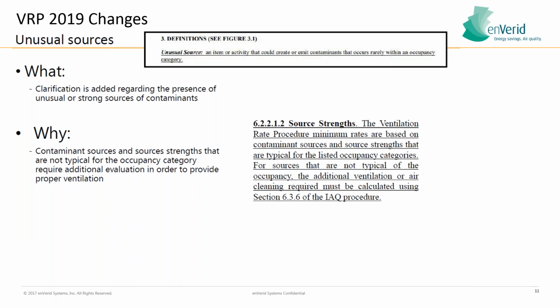I wanted to talk, industry-wide, a little bit about ventilation rate procedure changes in 2019. They redefined a little bit what unusual sources are and made it more clear that the ventilation rate procedure is based on contaminant sources and source strengths that are typical for standard occupancy categories. So for sources that are not typical of the occupancy, additional ventilation or air cleaning must be done using the indoor air quality procedure. An unusual source in this case is defined as an item or activity that can create or emit contaminants that occur rarely within an occupancy category.